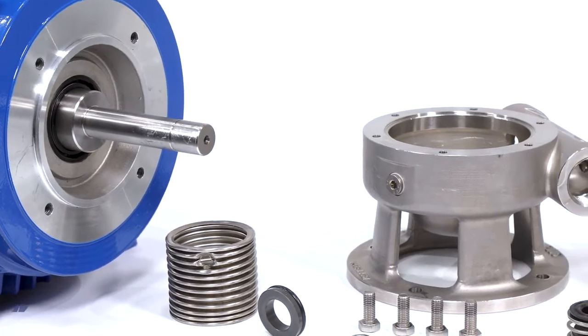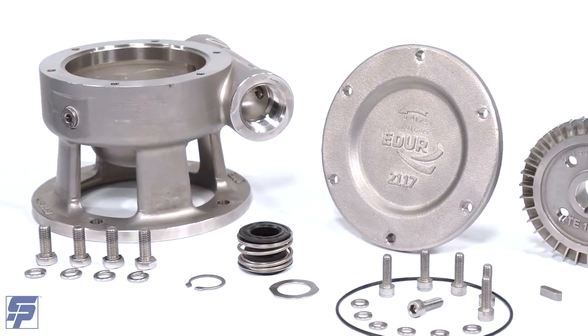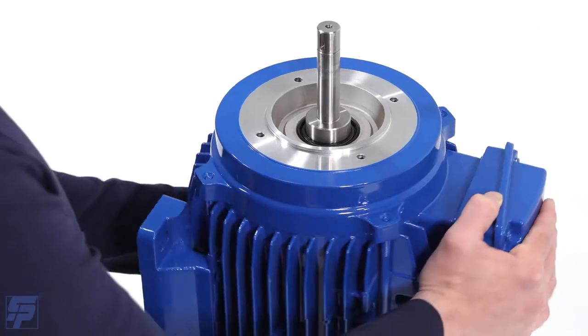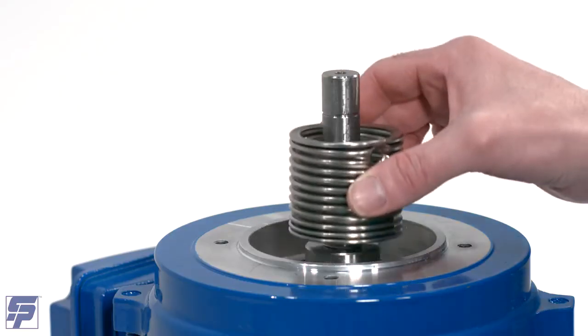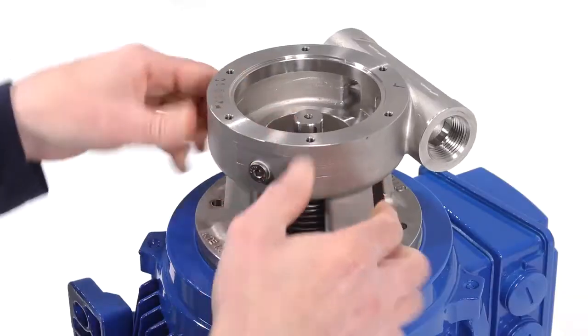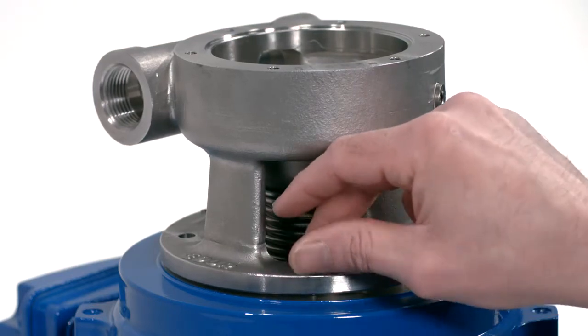The EDUR PBU Dissolved Air Flotation Pump is now completely disassembled. EDUR PBU Assembly. Place the motor on a workbench vertically with the pump foot facing you. If your pump uses a shaft guard, place it on top of the motor with the drain facing the bottom of the pump. Place washers on pump casing bolts to prepare them for installation. Mount the casing onto the motor in the correct orientation, lining up the four casing bolt holes with the threaded motor holes. Install four casing bolts and washers and tighten with an appropriately sized wrench.